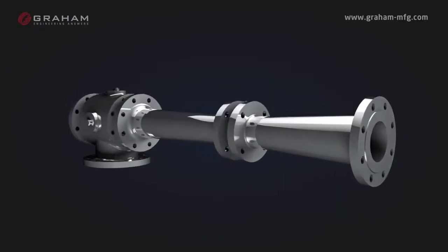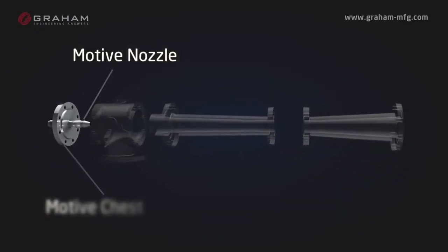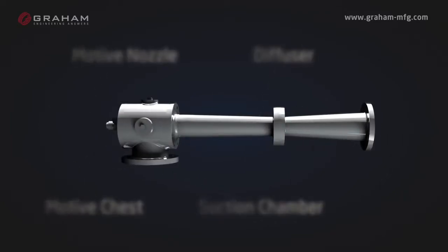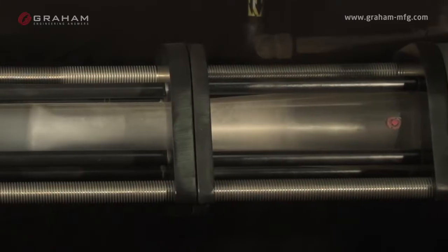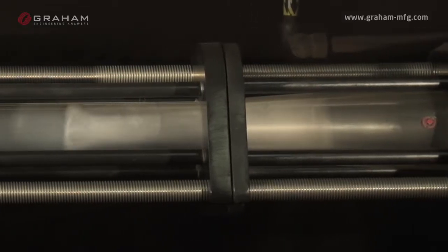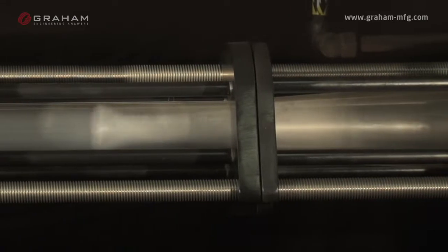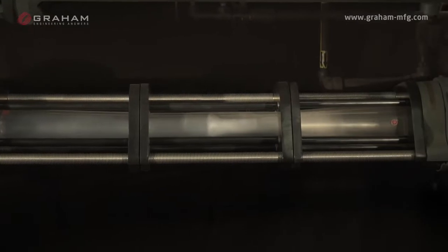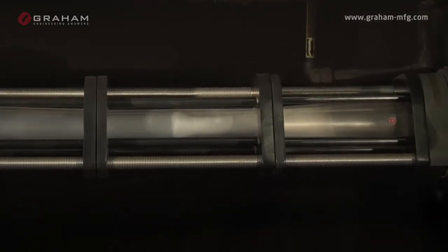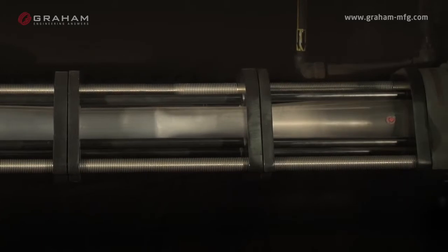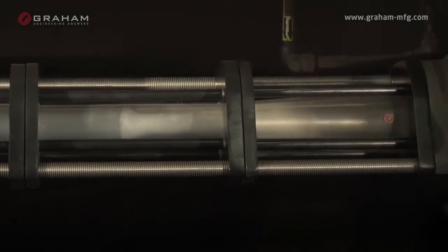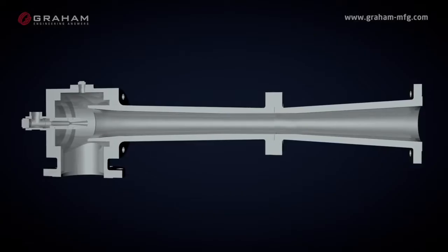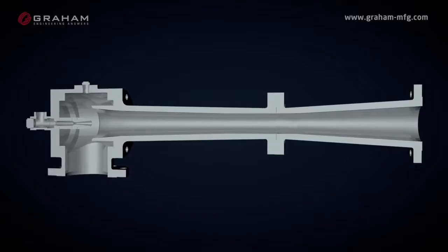There are four major components to an ejector: the motive nozzle, motive chest, suction chamber, and diffuser. An ejector works by converting the pressure energy of the motive fluid, otherwise known as potential energy, to velocity energy or kinetic energy. This is accomplished by the adiabatic expansion from the motive fluid supply pressure to the suction load pressure, as motive fluid flows through a converging-diverging nozzle, as you can see happening here in the glass ejector.